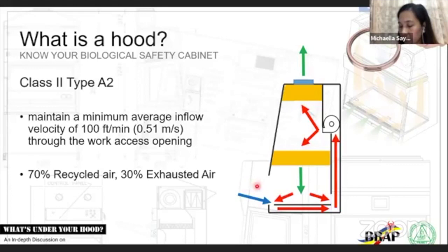Okay. So your clean air is distributed across the surface of your filter, producing a uniform downstream. Importantly, there's a downstream in this part. This is where you get your air curtain. So that air curtain prevents dirty air from going out. So if you do your smoke test, you will see your air should go in and down the front grill, not in and across the table, right? So in and down the front grill. It shouldn't go in and out. Now if ever your biosafety cabinet does that, inform your supervisor immediately and do not use the biosafety cabinet, okay?